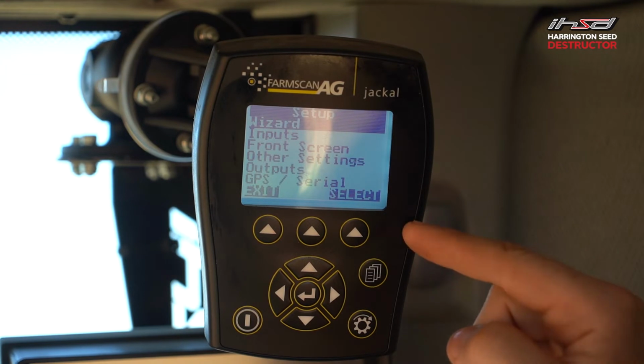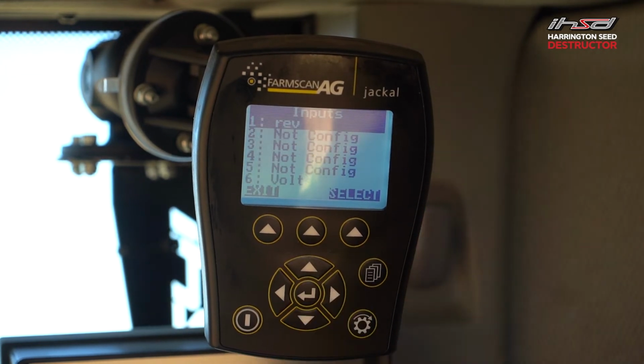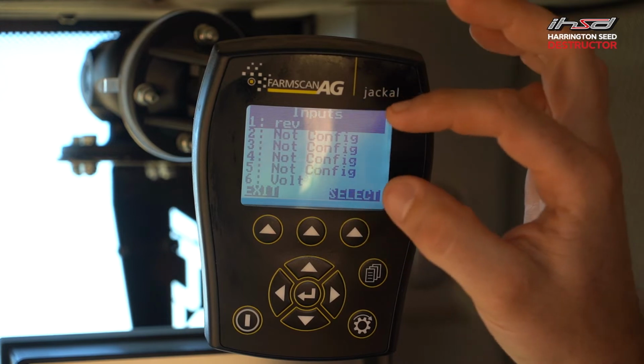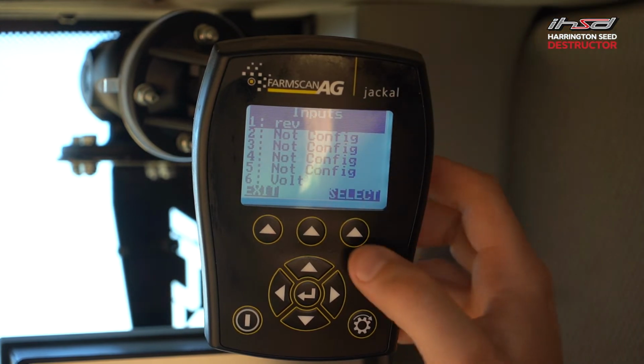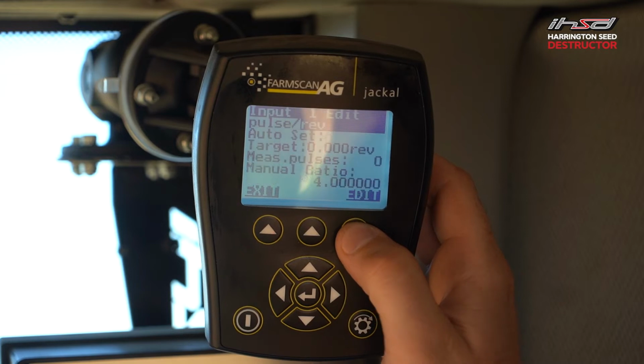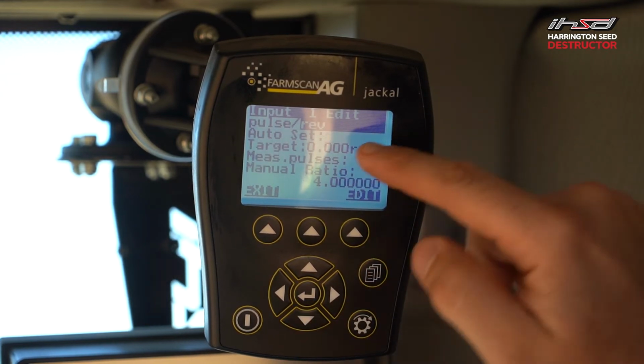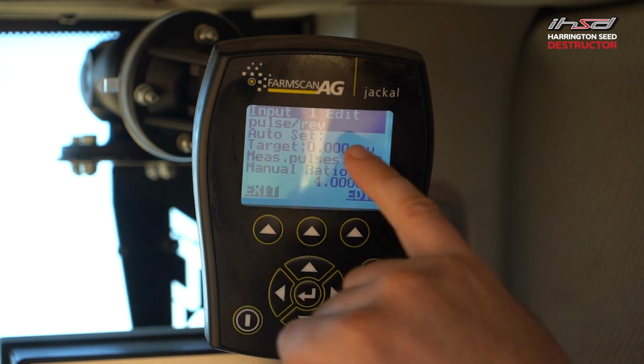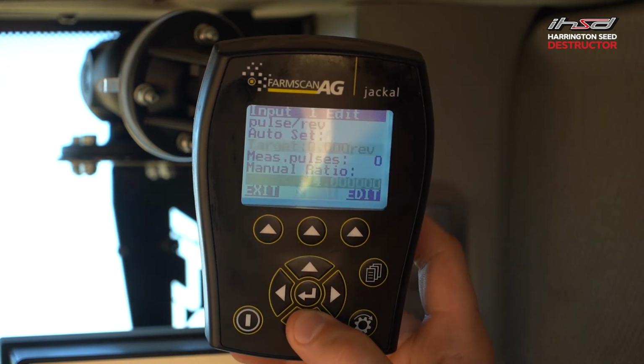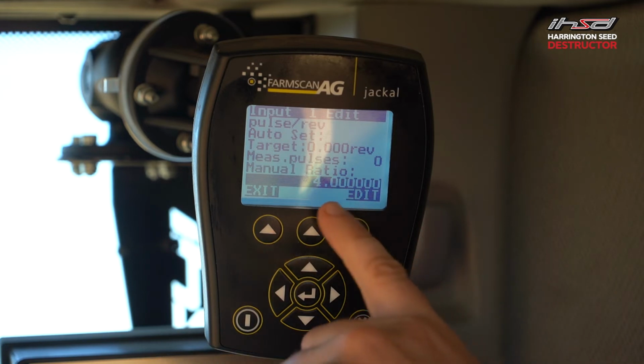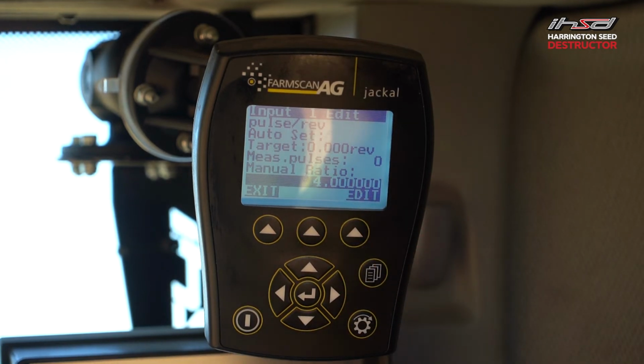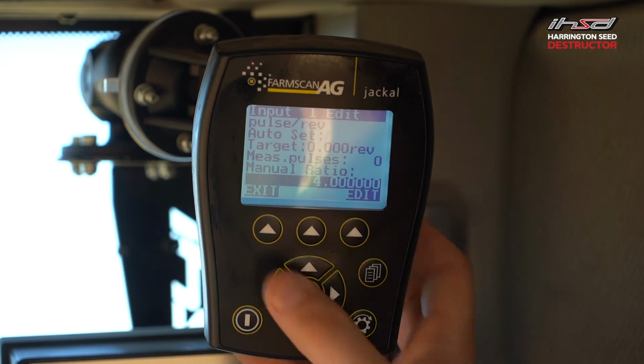If we go into press the setup button, going into inputs, you should have 2 inputs, 1 for revs and then 6 for volt. Going into revs or the RPM, the main important ones is to have pulse per rev set and then onto manual ratio. Manual ratio needs to be 4. We have 4 lugs on our speed gear on the shaft of the iHSD. So when we do, it counts for 4 times for every revolution.